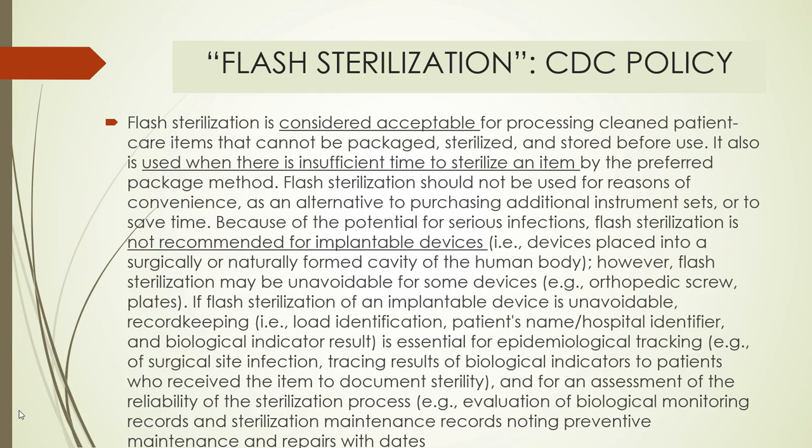Now, the Center for Disease Control does have a policy regarding flash sterilization, and you want to keep in mind that it is considered acceptable if the instrumentation is clean. And one of the problems you may have is if sets of instruments are being, quote, flash sterilized between cases, so that some other surgeon has just finished using that instrumentation. Sometimes the instrumentation may not be properly cleaned, and as a result the flash sterilization may not be effective, because when instrumentation is not cleaned, flash sterilization or any sterilization or disinfection may not work. So it's acceptable if there's insufficient time to sterilize by autoclave instrumentation or other objects by the preferred method.